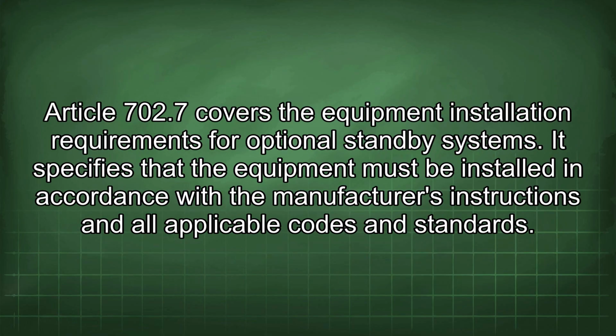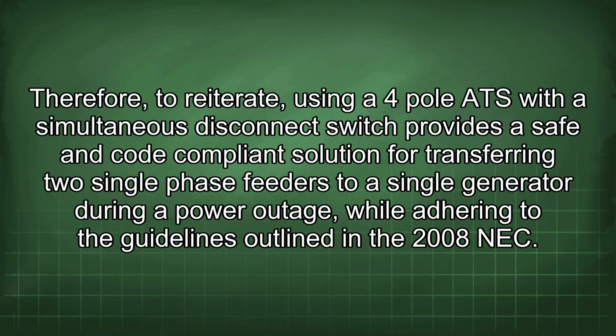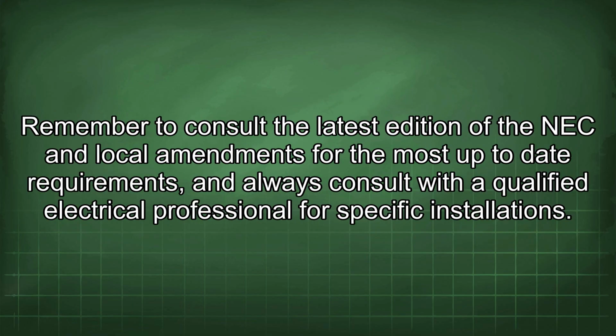Article 702.7 covers the equipment installation requirements for optional standby systems. It specifies that the equipment must be installed in accordance with the manufacturer's instructions and all applicable codes and standards. Therefore, to reiterate, using a 4 pole ATS with a simultaneous disconnect switch provides a safe and code-compliant solution for transferring two single-phase feeders to a single generator during a power outage, while adhering to the guidelines outlined in the 2008 NEC. Remember to consult the latest edition of the NEC and local amendments for the most up-to-date requirements, and always consult with a qualified electrical professional for specific installations.